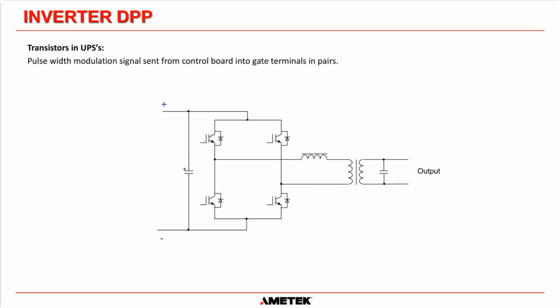But for example, if you didn't have bypass available when that fault occurred on a CVT system, that will push that current through that breaker without any issues and trip that breaker. So they are much better. A CVT transformer is much better at clearing a fault because we don't have to involve the IGBTs in that process.